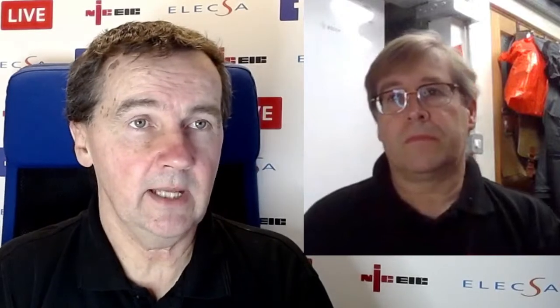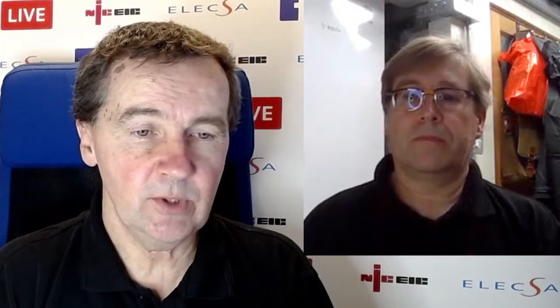So is it acceptable? Well, first thing is you've got to be able to meet the Zs of your protective device. You've got to meet the overcurrent protection granted by your protective device, and if this is the main incoming distribution circuit, which I'm guessing it is, you've got to consider volt drop, because that's going to have a detrimental effect then on all the volt drops of all your final circuits leaving the board as well. Anything else you'd add to that, Mark?